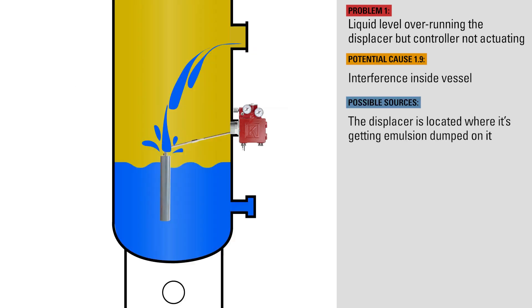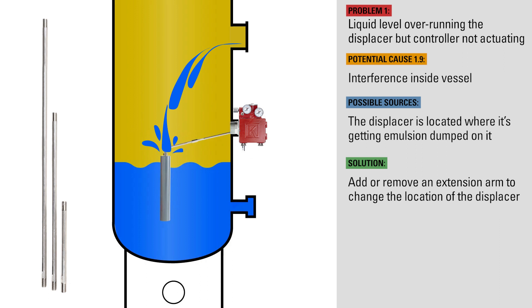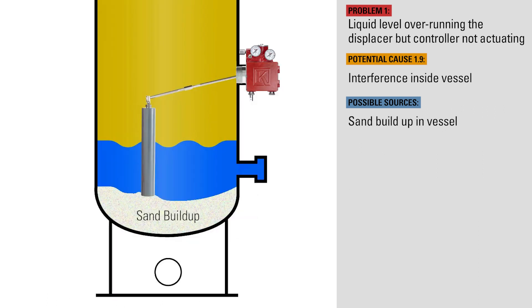If the displacer is located where it's getting emulsion dumped on it, this could hold the displacer down and keep the controller from actuating. To remedy this, if there's room in the vessel, add or remove an extension arm to change the location of the displacer. If there's a lot of sand in your system, it can build up inside the vessel over time to the point where it restricts the downward movement of the displacer. In this case, you'll need to shut in the vessel and remove the sand.